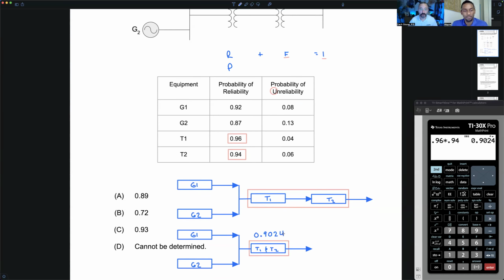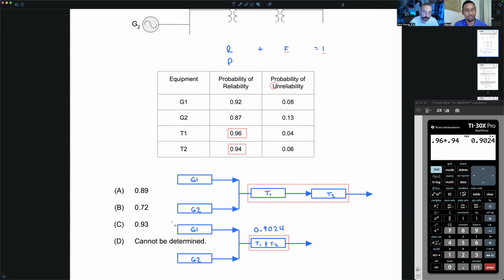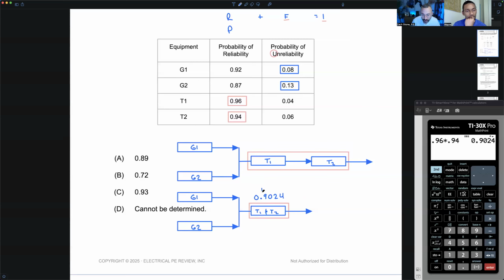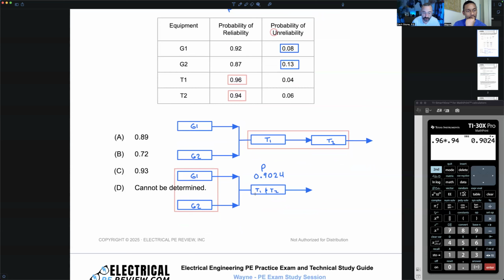Excellent. When we combine parallel blocks, instead of multiplying the probability of reliability, we actually multiply the probability of unreliability, or the probability of failure. So for generator number one and generator number two, I can find the equivalent probability of unreliability by multiplying these two values together. This is a probability value—we can call it P or R. Now we're going to calculate the new equivalent probability of unreliability for just the generators.